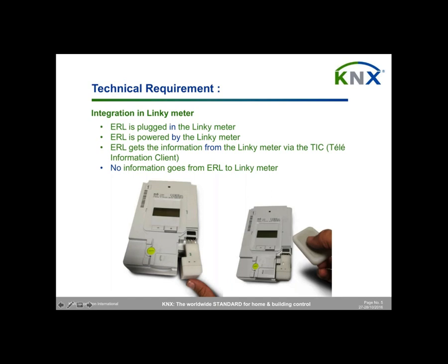What we can also see on the pictures is that we have remote devices which is linked to the ERL to make the push-button configuration, because when installed, the ERL module will be under another cover plate that will cover all the meter on the ERL, and then we have no more access to this module. And to be able to make the push button configuration, we need remote HMI.